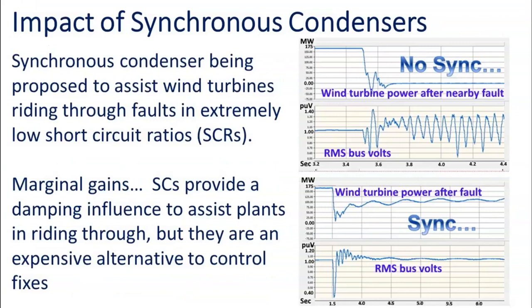So the top plots of power and RMS volts show a case where there's a fault near the wind plant where there was no synchronous condensers and the short circuit capacity was pretty low, and of course the wind turbines tripped out on their low voltage ride through and the RMS bus volts went crazy. But when you put a sync condenser in, as Nick showed, it helps things a lot better.